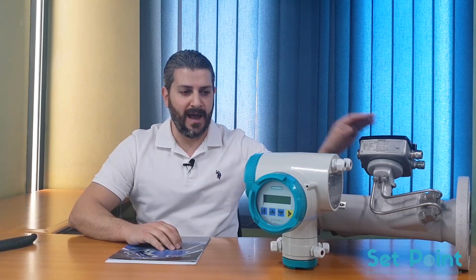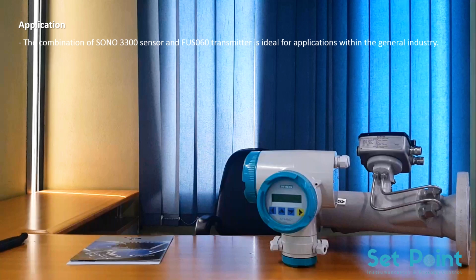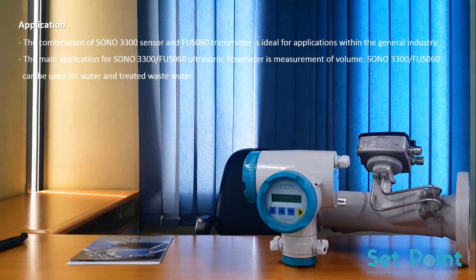Here we have the Sitrans FUS SONO 3300 flow meter and the Sitrans FUS060 transmitter. So let's have a brief look at this combination of the sensor and the transmitter. The combination of the SONO 3300 sensor and FUS060 transmitter is ideal for applications within general industry. The main application for the SONO 3300 FUS060 ultrasonic flow meter is measurement of volume, and it can be used for water and treated wastewater. Measurements are independent of liquid temperature, density, pressure, and conductivity. Transducers cannot be replaced, and the measuring principle is transit time.